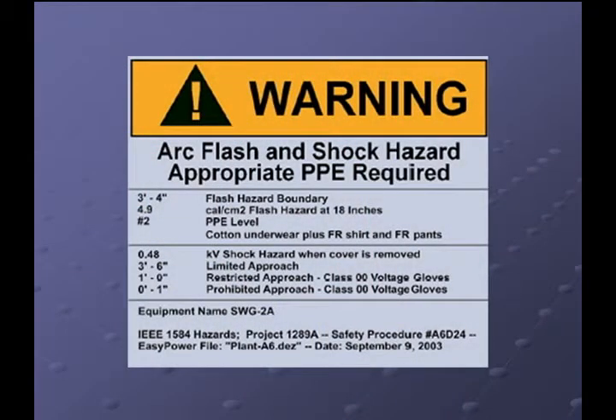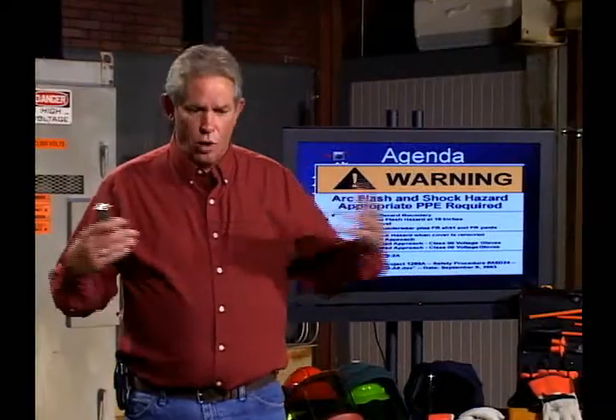The next one says there's 4.9 calories per centimeter squared at 18 inches. Now that 18 inches is a working distance, from your chest to the equipment, and it doesn't consider any door that happens to be in the way. So if we were to get closer, the calories would go up exponentially. If we get further away, the calories go down exponentially.